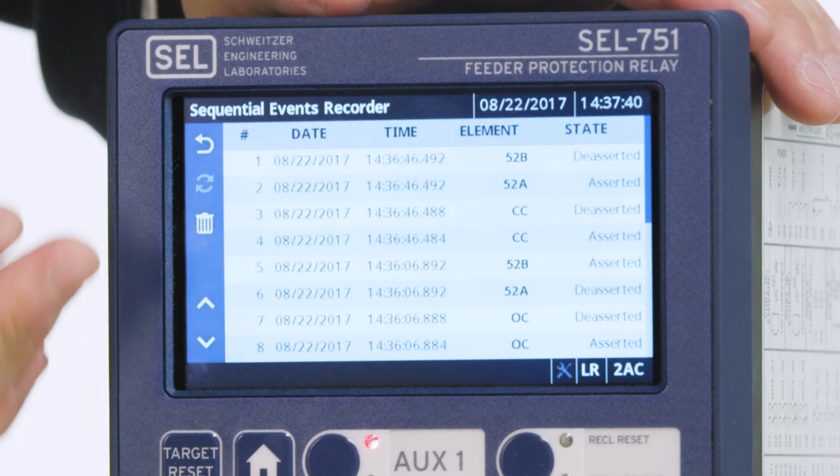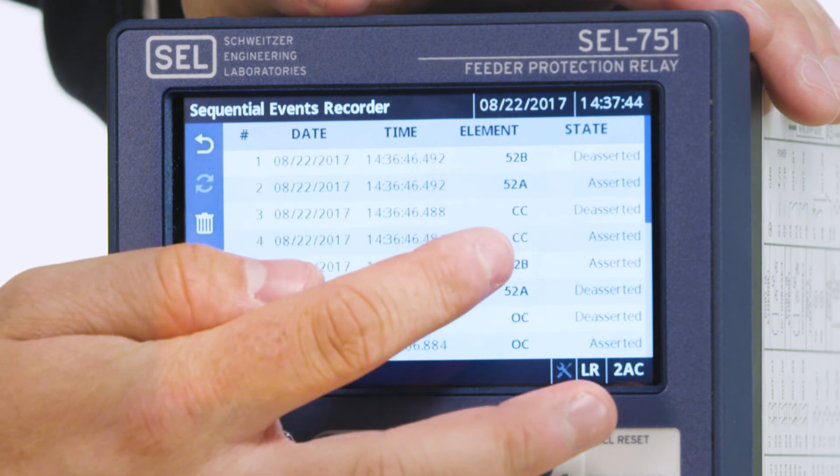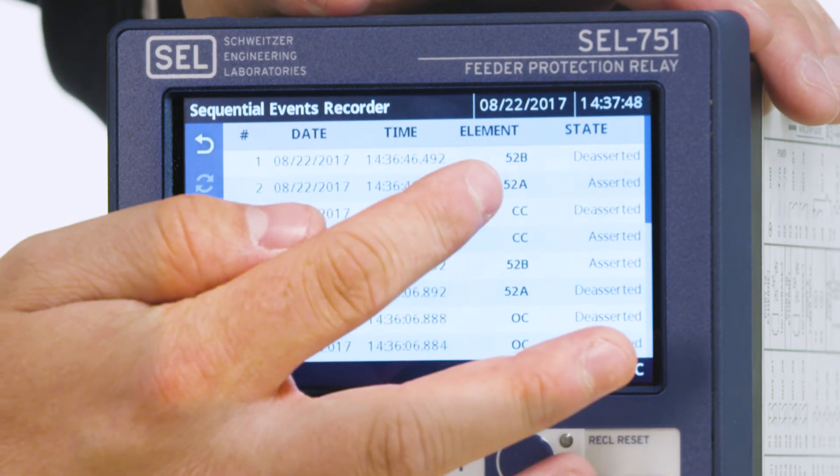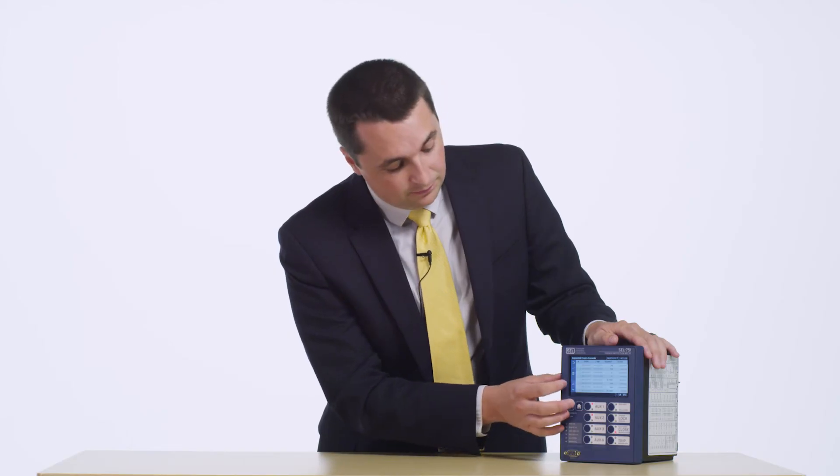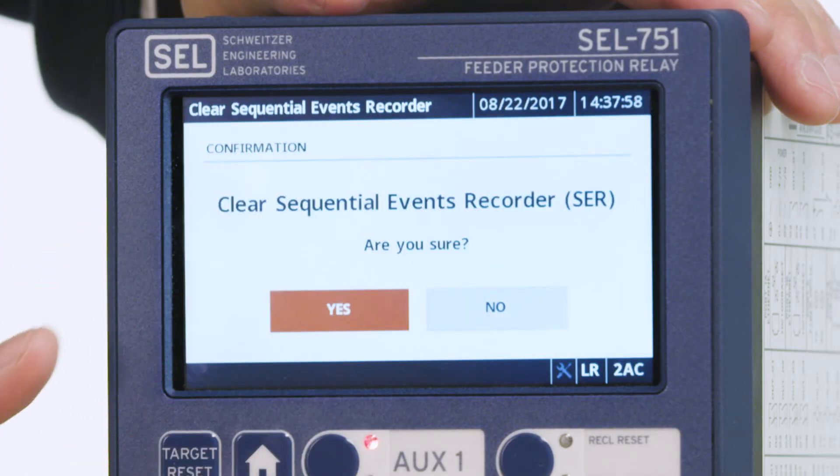At the top of our list here, you can see the close command was issued to close the breaker and the 52A contact was asserted showing that the breaker was closed. To clear the SER, simply press the trashcan icon here and verify that you would like to clear the SER.